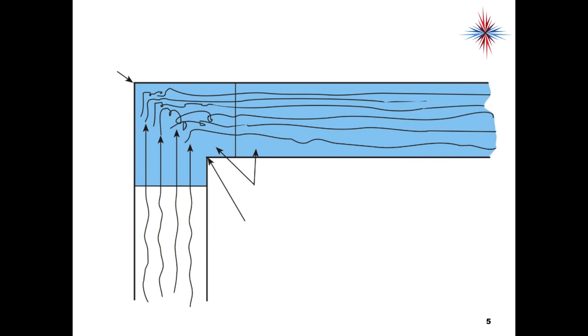So what this slide is showing you is a square throat elbow without any turning vanes. We're going to talk more about turning vanes, but they're basically little pieces of metal we put in a 90-degree elbow to help the air change direction. The air hits the heel of the elbow and becomes very turbulent, and you can see that at the top left-hand corner. The air will crowd at the heel, and there will be a low pressure area at the throat.